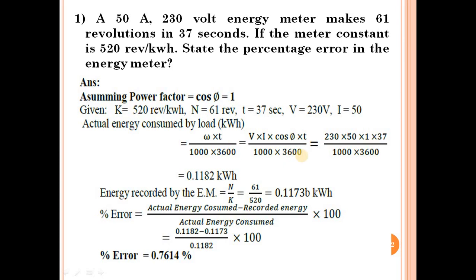So that is your actual energy consumed by the load — 0.1182 kilowatt hours. Now the original energy meter constant formula is k = n / e, where k is the energy meter constant, n is number of revolutions, and e is energy recorded by the energy meter. So energy recorded by the energy meter: e = n / k.